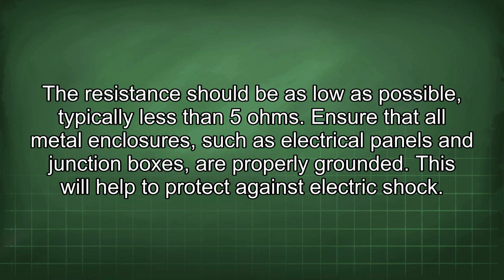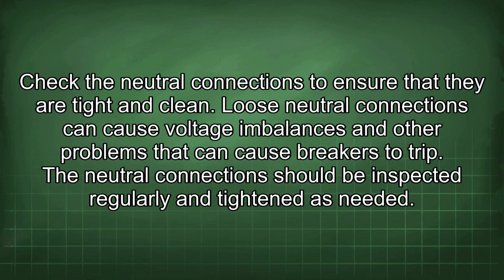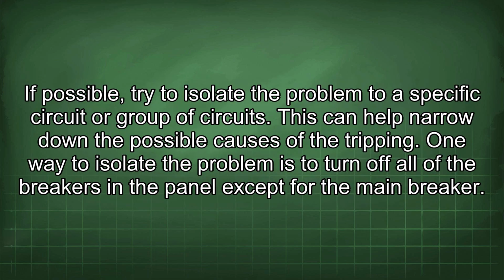Ensure that all metal enclosures, such as electrical panels and junction boxes, are properly grounded. This will help to protect against electric shock. Check the neutral connections to ensure that they are tight and clean. Loose neutral connections can cause voltage imbalances and other problems that can cause breakers to trip. The neutral connection should be inspected regularly and tightened as needed. If possible, try to isolate the problem to a specific circuit or group of circuits. This can help narrow down the possible causes of the tripping.